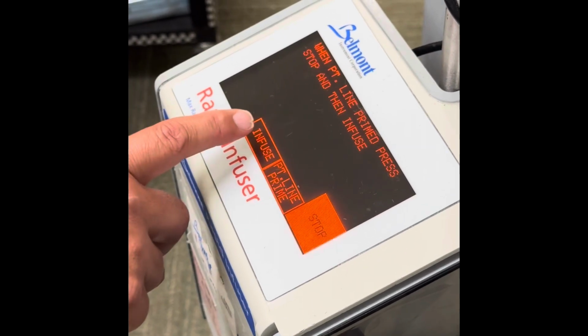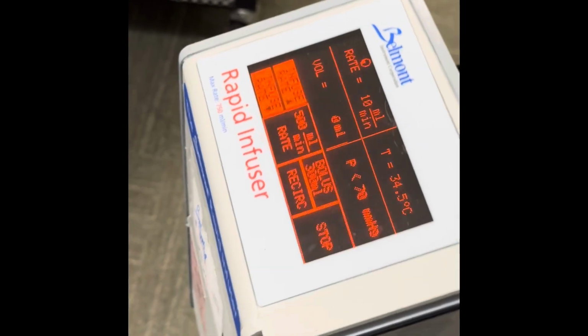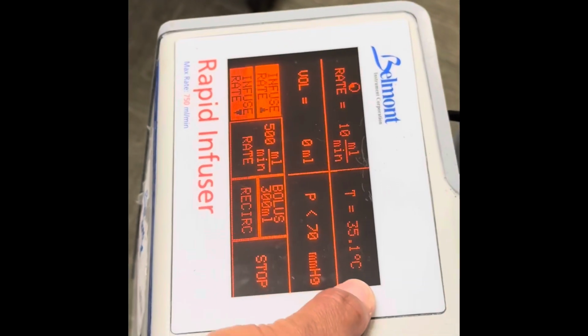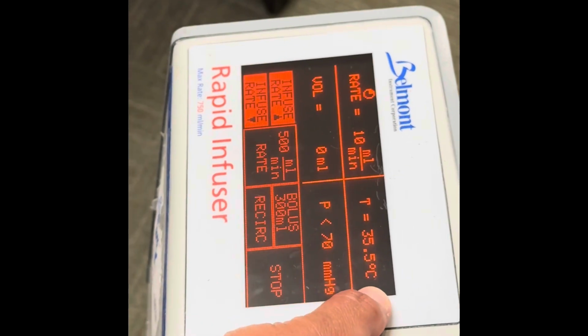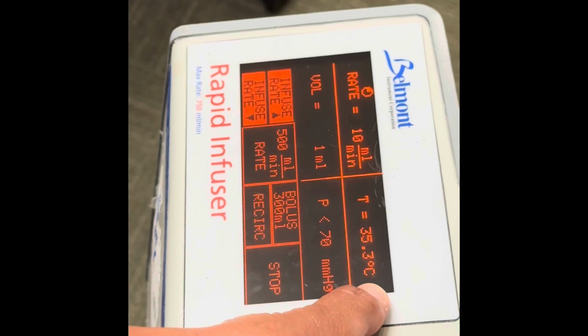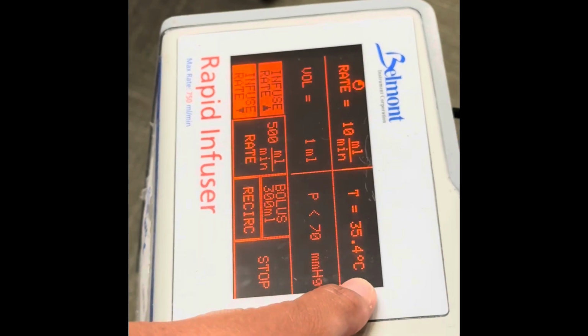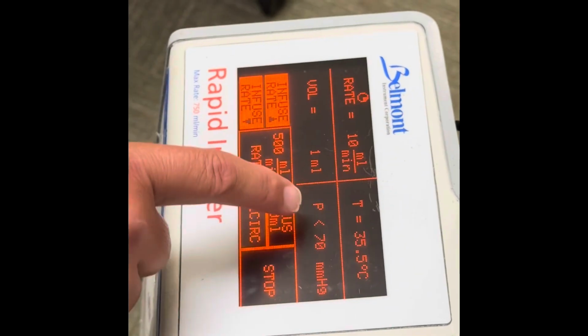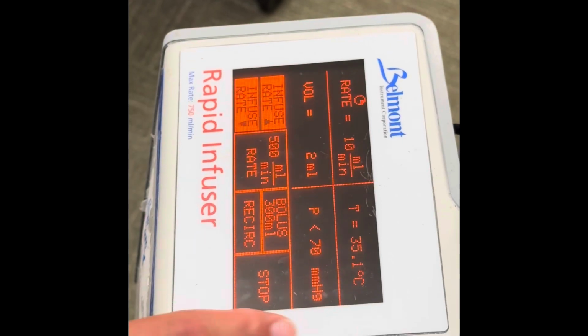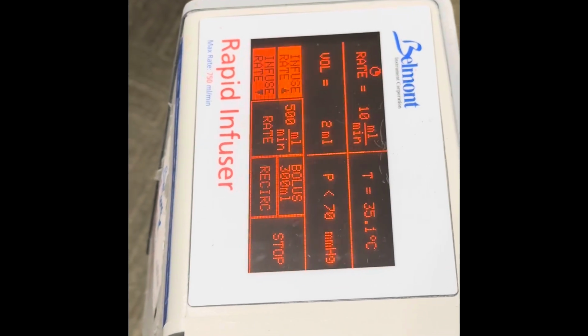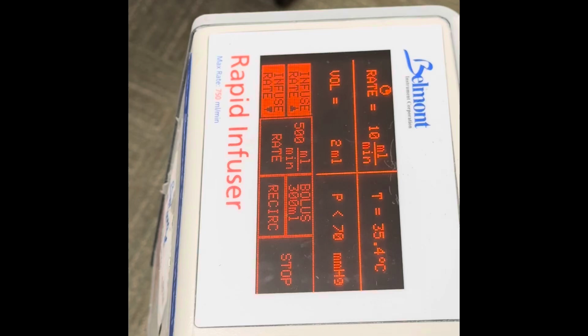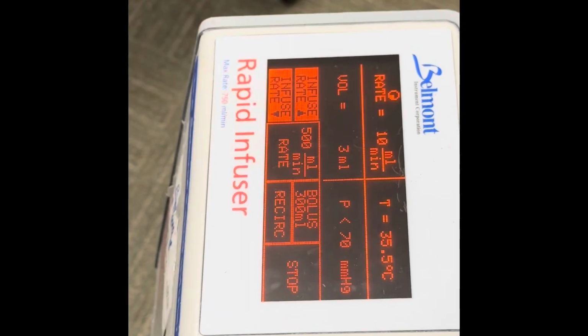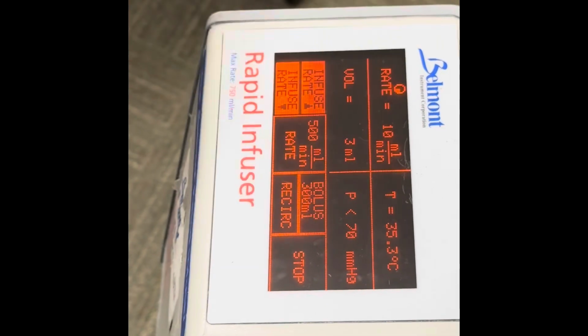But we're going to tap infuse and we're going to get the screen that gives us lots of options. The temperature of the Belmont is located here. Please remember, if it is not plugged in, it will not warm. And if it's not plugged in, it will tell you that it's not warming. This is your pressure calibration. This will tell you how fast your machine is actually working. We have our volume, so it'll keep tabs of our volume, and then we can adjust the rate.